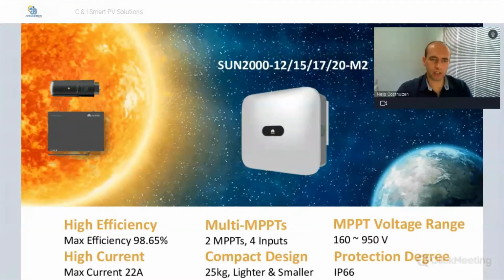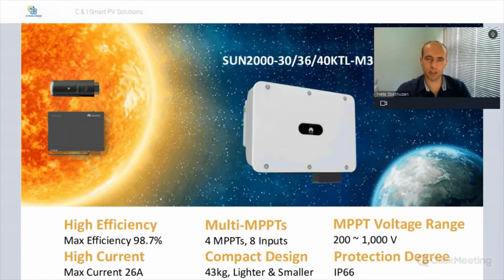This page is a product highlight of the 12 up to 20 KTL M2. Note the maximum efficiency of the inverter is 98.65%, with 2 MPPTs and 4 inputs. The MPPT voltage range is between 160 and 950 volts, and the maximum current supported per MPPT is 22 amps. A nice feature about this specific inverter is that it is 25 kilograms, so it's lighter and smaller than most of the competitors, which means it can be handled and installed by a single person, with no need for additional expenditure on labor.